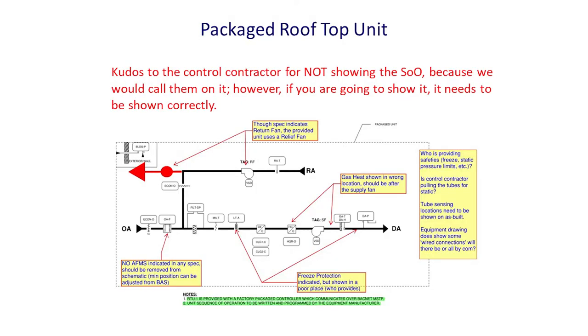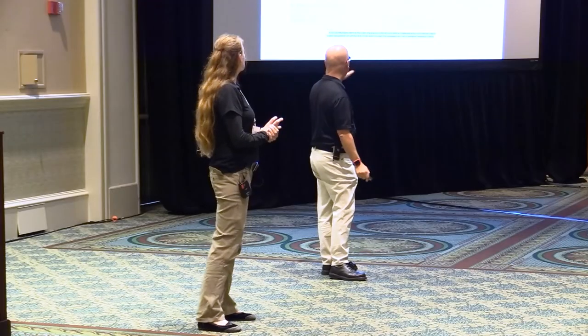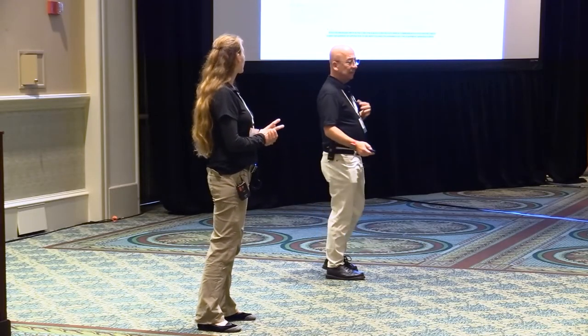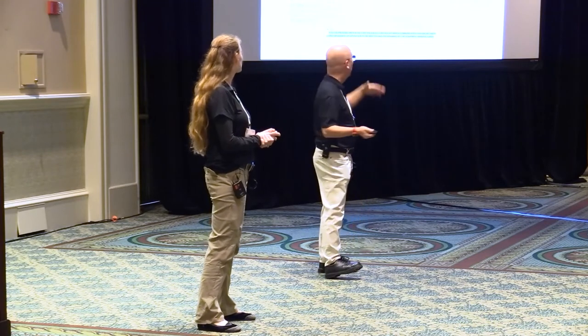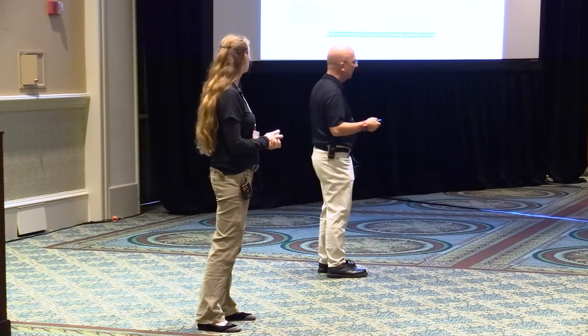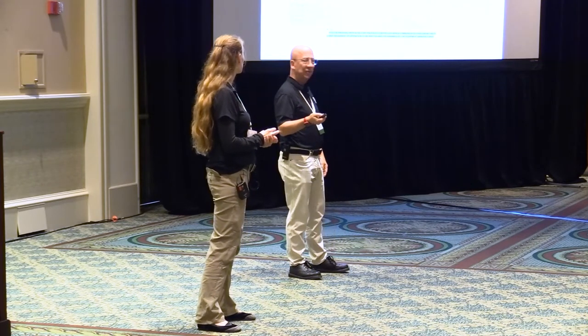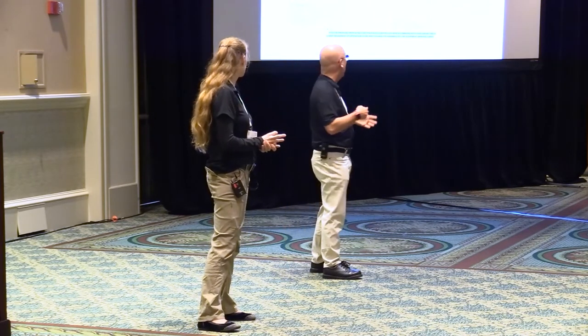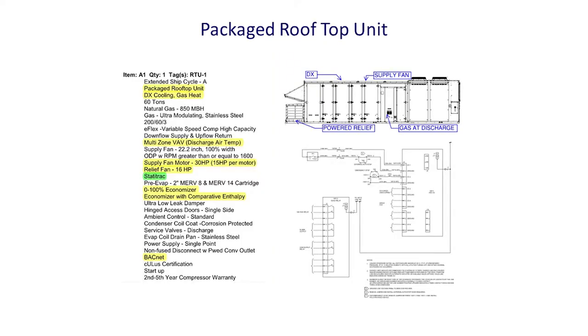So the same thing we spoke about, like using Bluebeam, was similar to what we used here: if you are going to show a schematic, it should be shown accurately. And there were a number of things that they had wrong. They had the gas heating in the wrong place. They showed a return fan, but it was really a powered relief fan. There wasn't an airflow monitoring station, and we're saying, how did we determine all this stuff? Well, we actually went and reviewed the submittal to find out what all the components were that were actually being provided. And that gave us a better understanding of how it works. And again, a system schematic should be accurate.